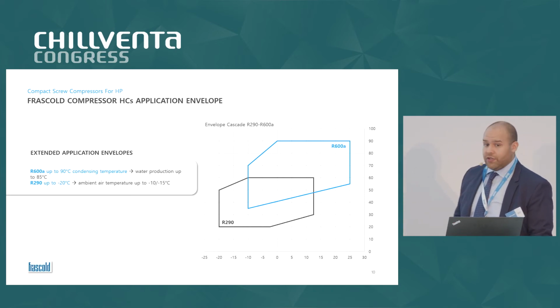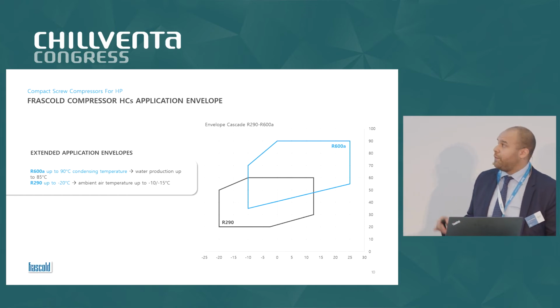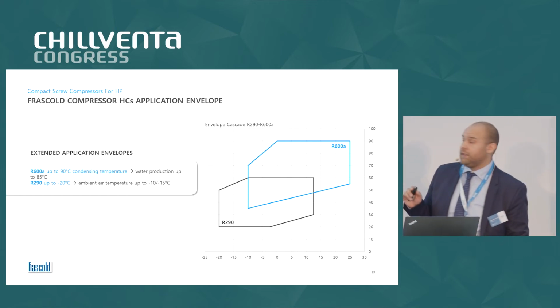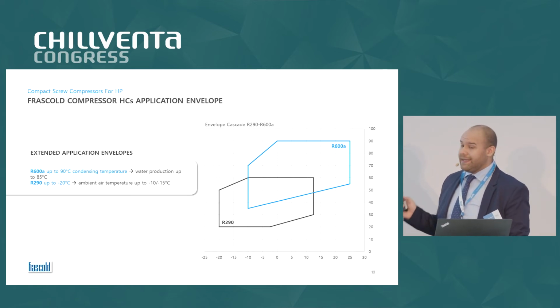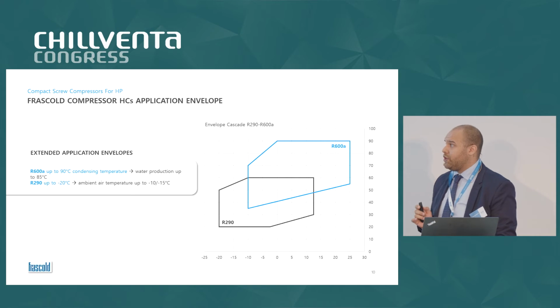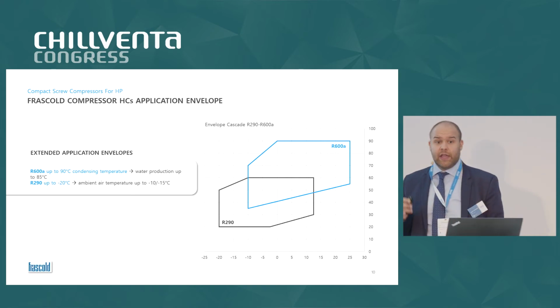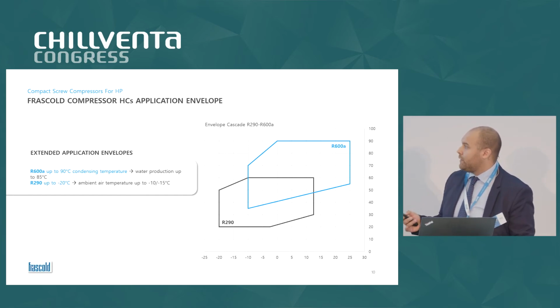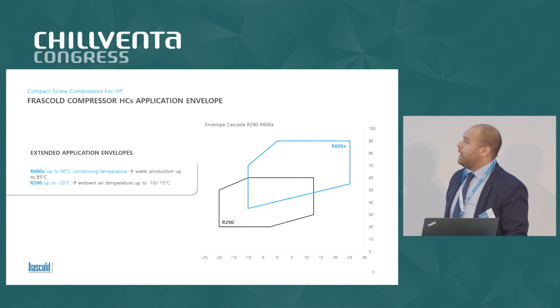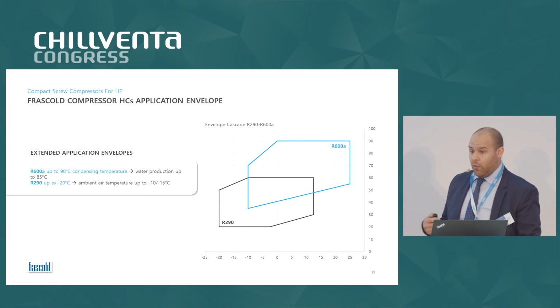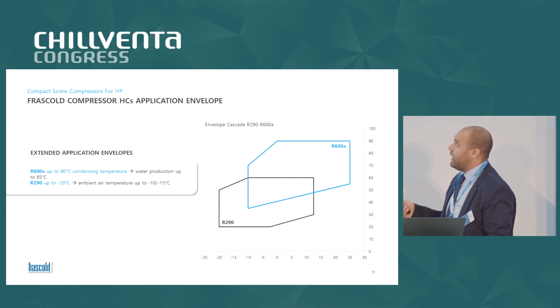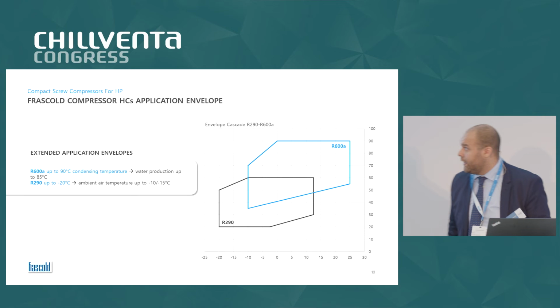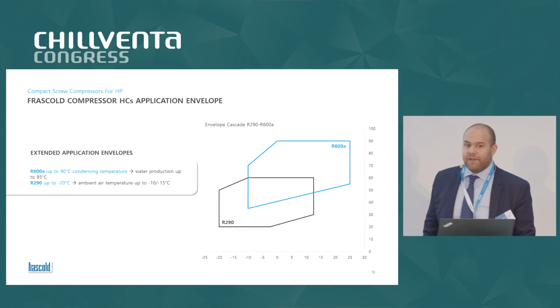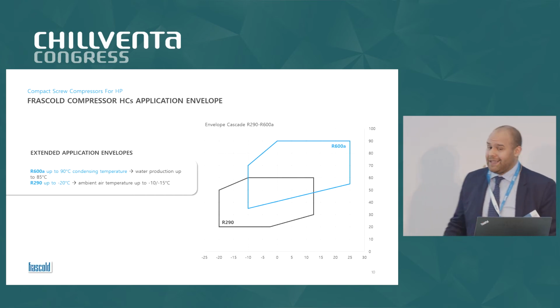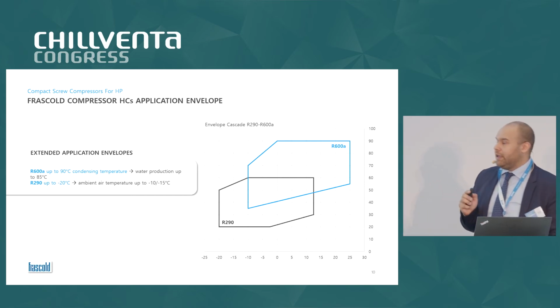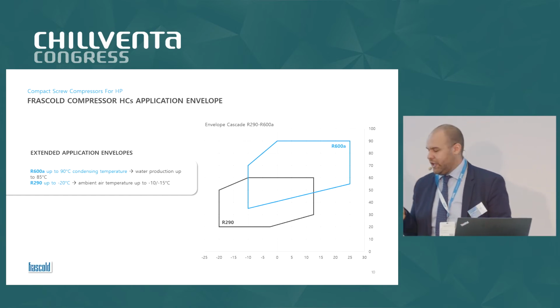You can see the application envelope of our CX compressor, compact screw compressor, for two different refrigerants, R290 and R600A isobutane. You can see these two refrigerants because the system of our customer, Solid Energy, is a cascade system to produce an air-to-water heat pump that is able to evaporate at very low temperature using the low stage in R290 and to deliver very high water temperature, considering that the high stage is in isobutane, which is able to condense up to 90 degrees. So it is the perfect match, a cascade system, isobutane and propane, to realize an air-to-water heat pump that needs to deliver water up to 80-85 Celsius.